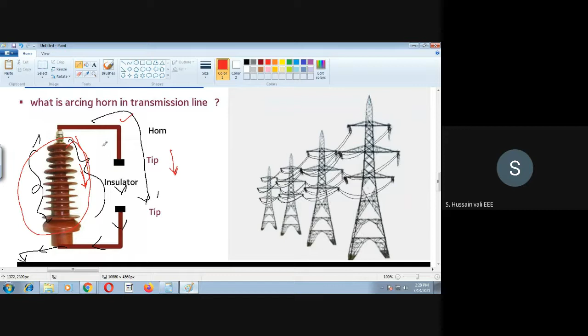So rather than getting these damages, you will have another extra protection in the form of the arcing horn, that is in this path. If you have this path, then the advantage is that rather than going in this direction, the flashover will occur in this way, so that this part will not have any effect or will not get damaged. Now you are saying that for equal voltage distribution you will use the guard ring. Is it correct? Yes sir.